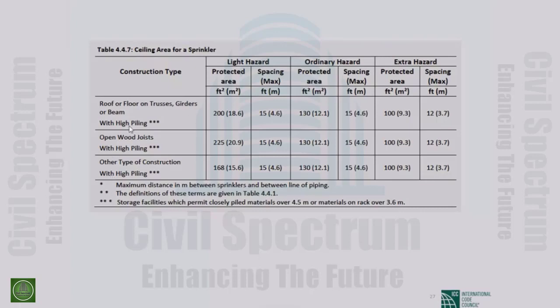But in our country, in the last few years, in different garment industries we have visited, mostly they design with roughly 100 to 150. It is too high density. Actually, the high density does not give you extra safety. It gives some extra money, extra design, but it does not give extra safety because whatever the design value, it should be within the limit of the design value. So you can use 10%, 20% as a safety factor. You should not make it 100% safety factor in no case.